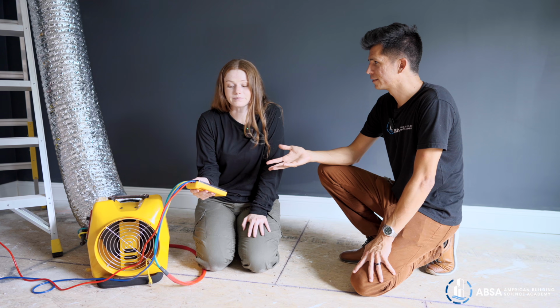Right. That's bad. So I'm guessing this is definitely not up to code. Right, so the code says you can have 4 CFM of leakage per 100 square feet of house. So we did the math, it's definitely over. Okay, gotcha. So we definitely got to figure out if there's some major leakage or if it's just a bunch of little leaks that they need to attend to. Yep. Okay, wow.